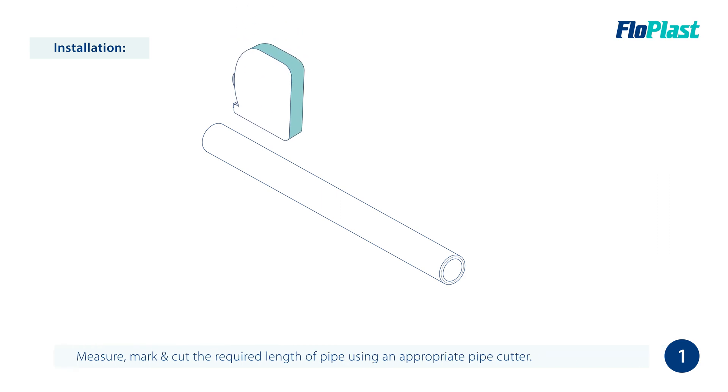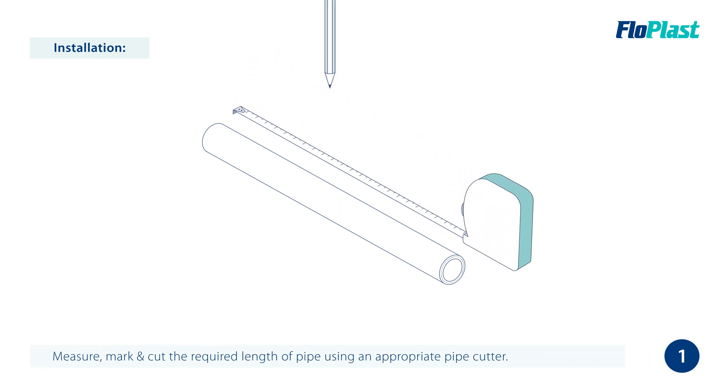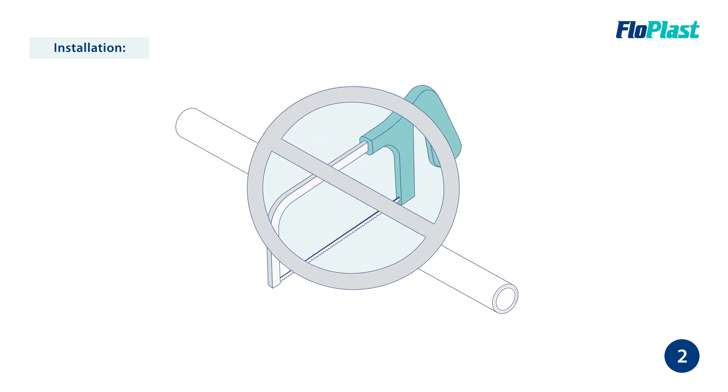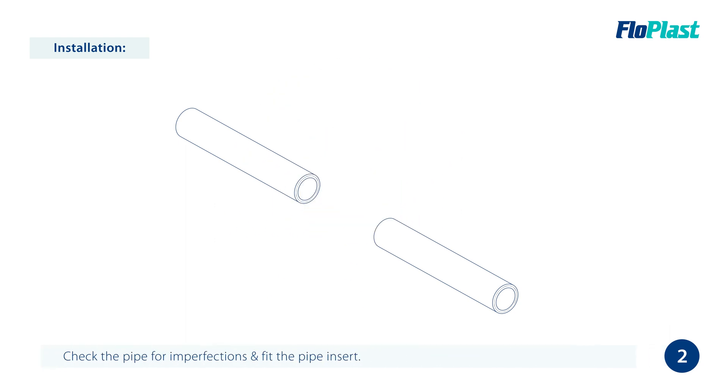To install the product, the first thing you need to do is measure and mark the required length of pipe. Once marked, cut the pipe using an appropriate pipe cutter. It is important not to use a hacksaw for this task. To ensure a good fitting, make sure to check the cut pipe is free from imperfections.